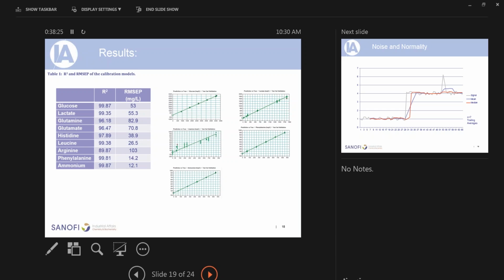You can see from these charts that we were able to build some pretty good calibrations. Now, we haven't been able to replicate these results on any other Raman spectrometers. It's my own personal view that this instrument is giving us between 10 and 20 times more sensitivity than the other equipment we evaluated. So things like glucose and lactate we can measure spectacularly well.